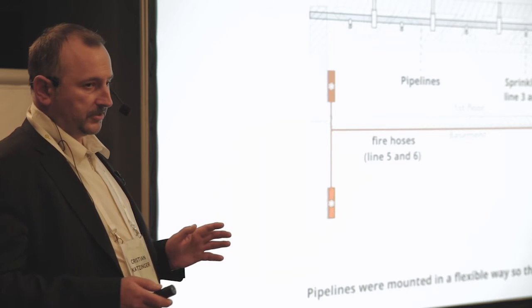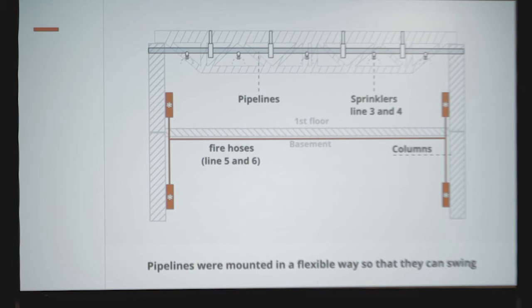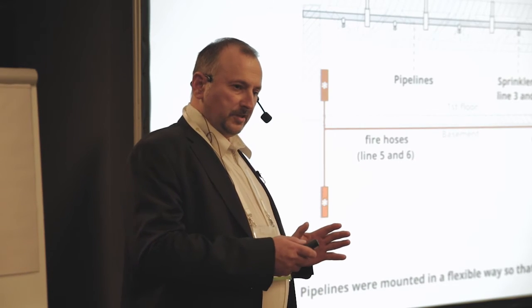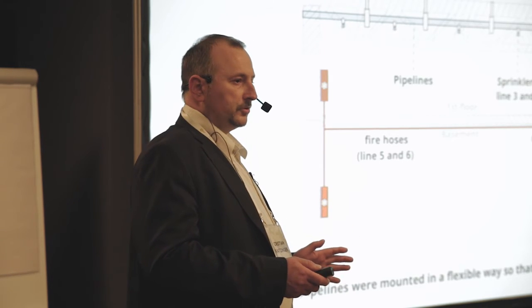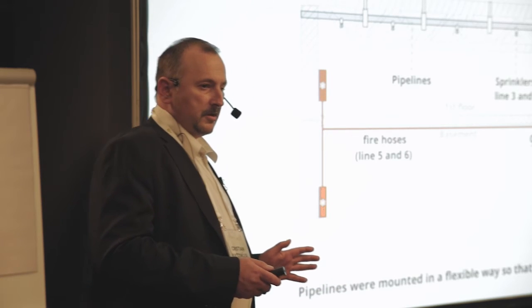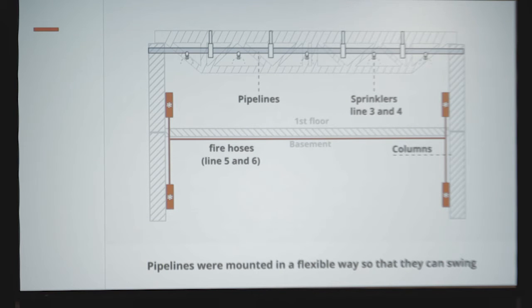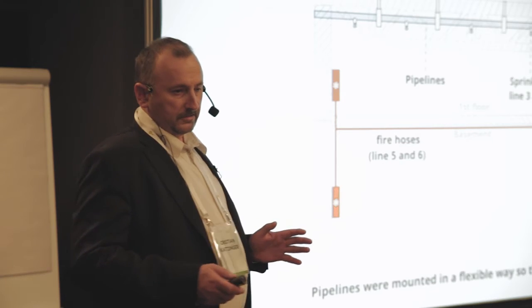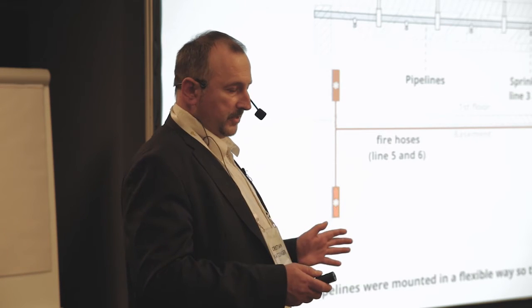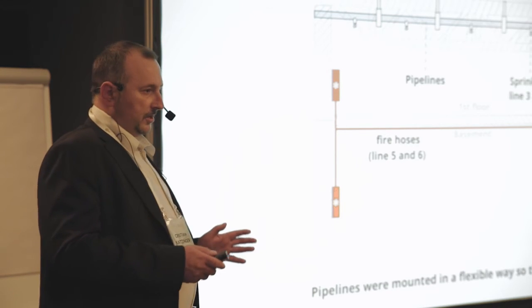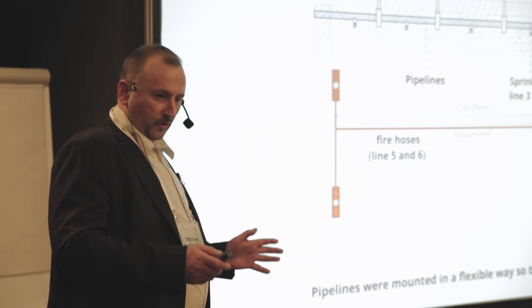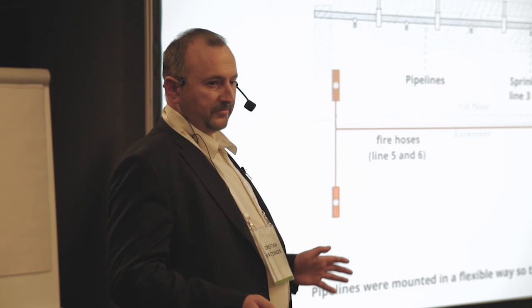That's one part. The other part, we've got here a sprinkler system. I explained that there are pipes mounted under the roof, but these aren't the pipes for the fire hoses on lines 5 and 6 where the alarm came from, but the pipes from lines 3 and 4. Even if there were a leakage inside a wet system, you would see the problem immediately, because a sprinkler which is breaking opens a valve, and such a sprinkler at 1 bar pressure releases about 80 liters per minute of water downwards. And 80 liters is a lot of water. As you can imagine, in a minute, it's half a bath tub.